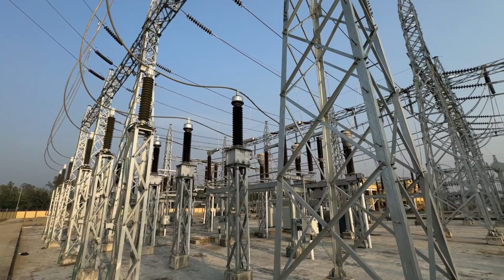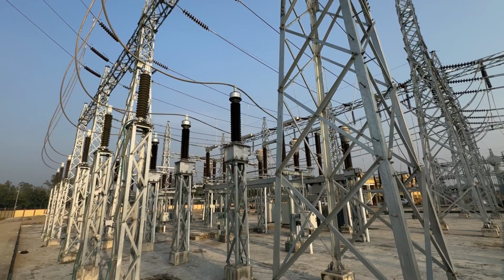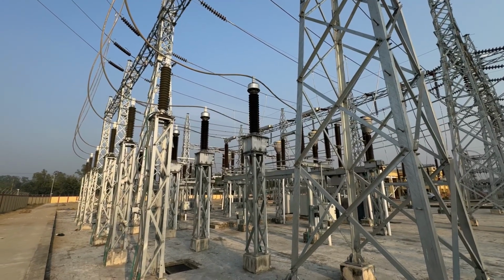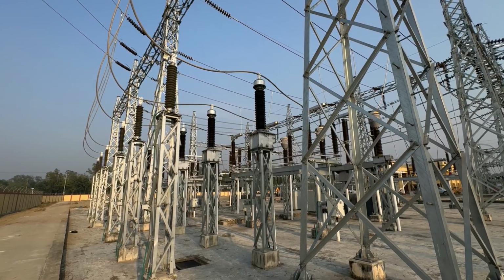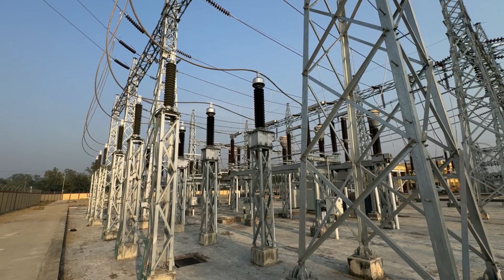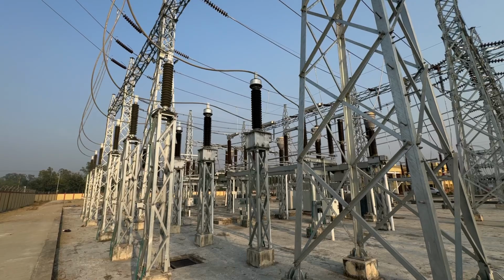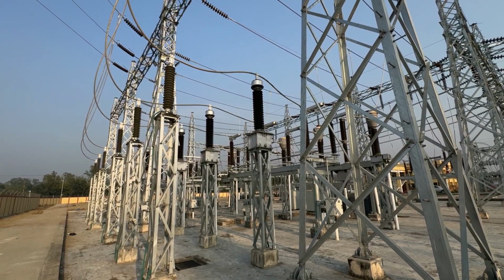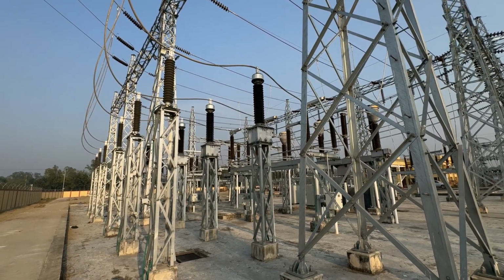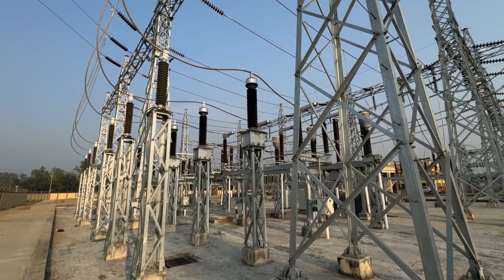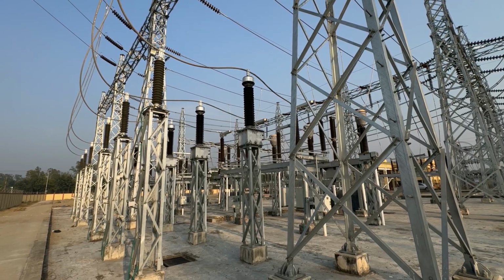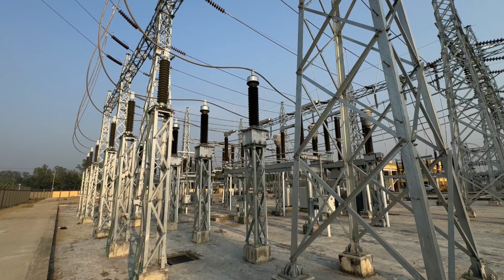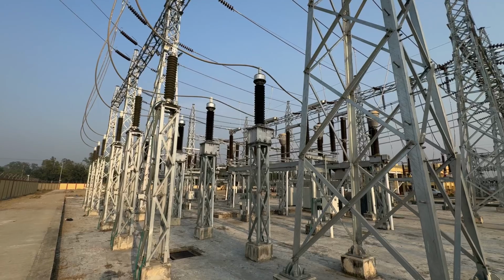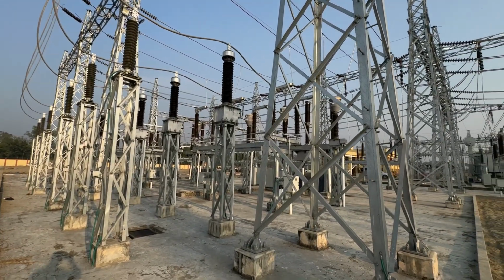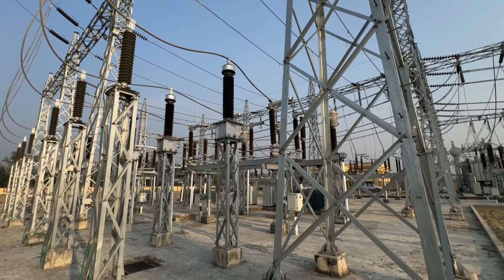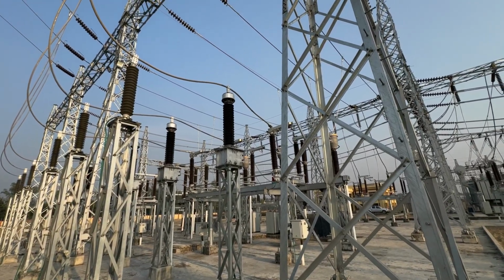The voltage ratio of the primary side of the transformer is 132 kV and the secondary side is 110 volt. It is a system voltage, but for each phase the primary side is 132 kV divided by root 3, approximately 76 kV, and the secondary side is 110 divided by root 3. Normally the system voltage is 132 kV, but the phase voltage of each phase is approximately 75 to 76 kV. But the question is, how does a CVT work?